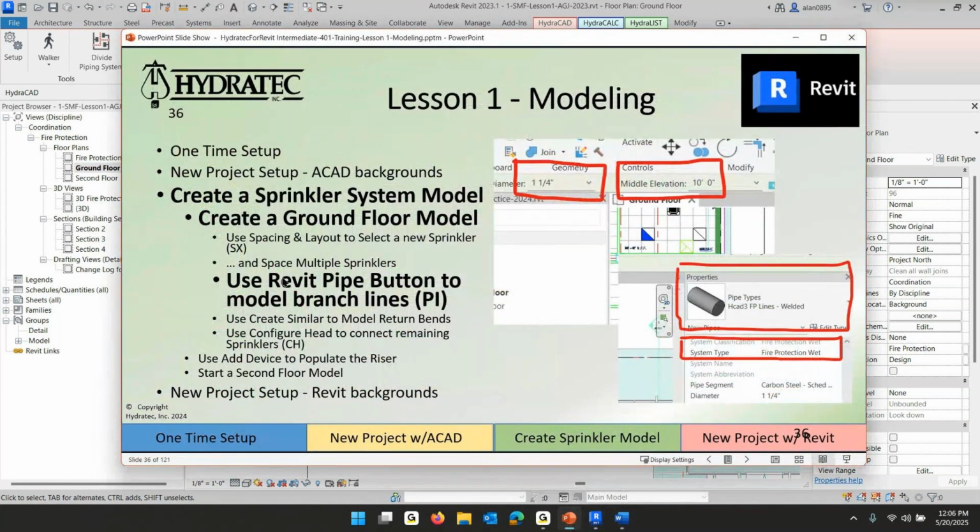Okay, so I'm going to use the standard Revit tool for pipes. Shortcut is PI, or I can go to the systems menu, the plumbing and piping panel, and then pick on pipes there. But the important thing is, when you go to do a sprinkler, you need to do 2 things: what type and how high. When you go to do a pipe, there's 4 things: the diameter, the height, the type of pipe, and just check that the system is a fire protection pipe, not a hydronic supply or a plumbing sanitary pipe or something like that.